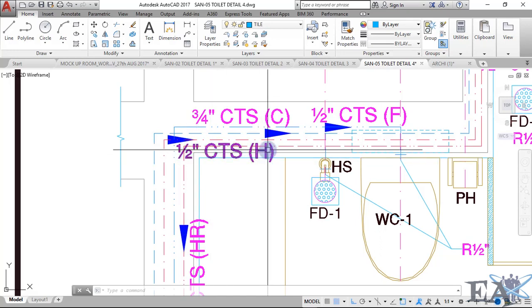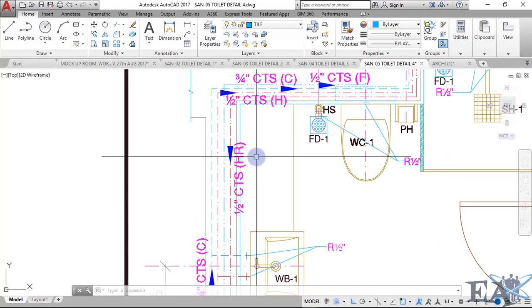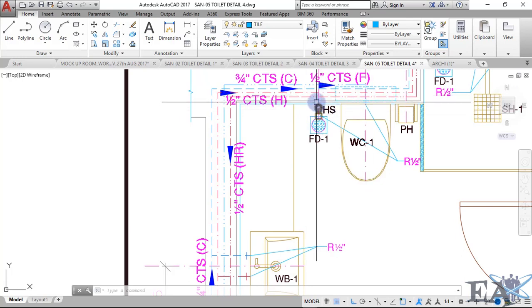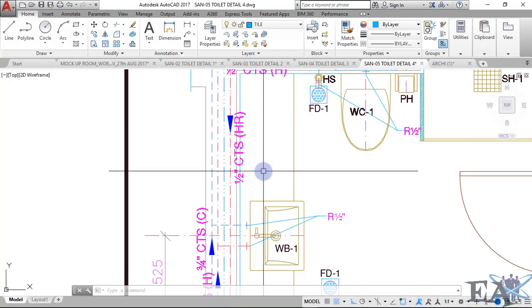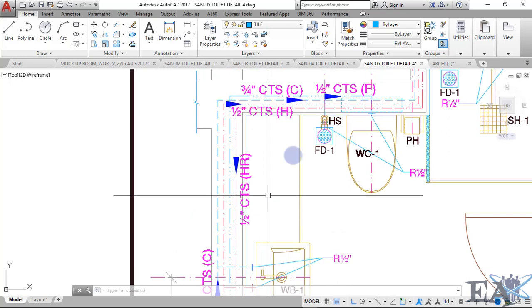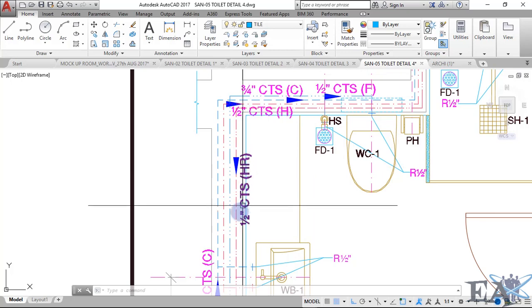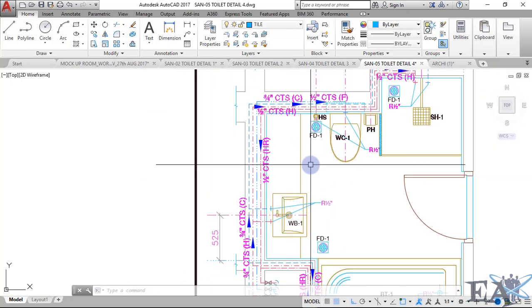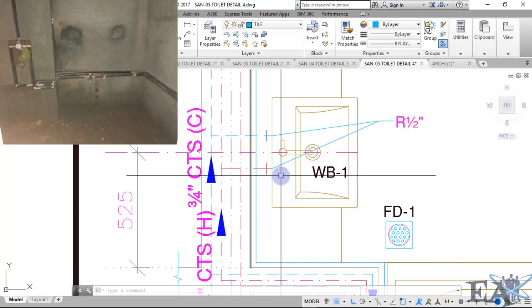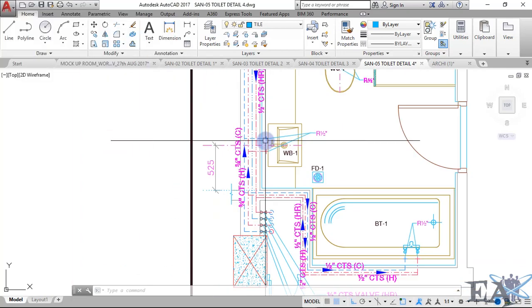H is for the hot line — you have half-inch hot water pipe — and HR is the hot return line. The hot water continuously circulates from the heat pump or heating mechanism to the building and back, so you have two hot water pipelines: one supply and one return. In total you have pipelines for cold, flush, hot, and hot return. These pipelines are placed inside the wall, and the wash basin will have two pipelines — one hot and one cold.